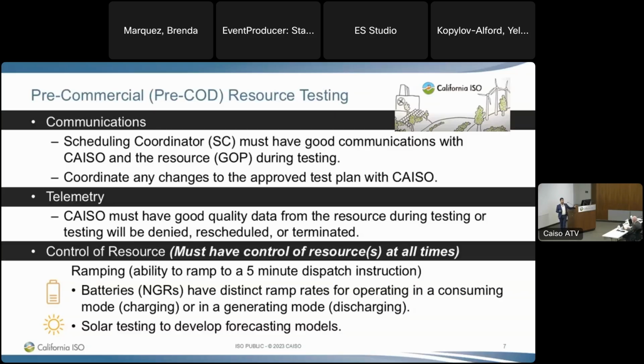And they can. So with these IBRs, with the controllers, with the batteries and the solar sites, what we're finding is when we call you and we want you to take manual action on that resource, there's multiple things that happen. There's some cases where they're like, well, I actually don't have control of the resource remotely. I'm actually going to have to send somebody out there. It's going to be 2 hours until I can get somebody out there. So what we have to do in those situations is go, okay, you're causing a real reliability issue on the system. We start coordinating with the local utilities to look at opening breakers.